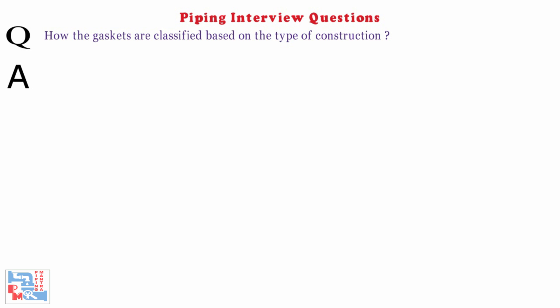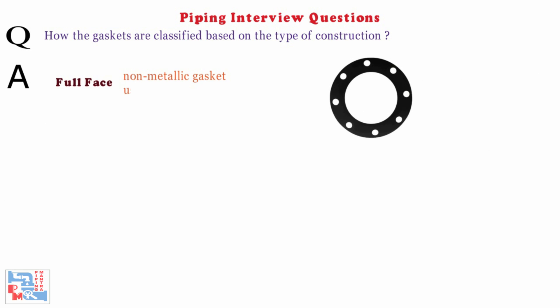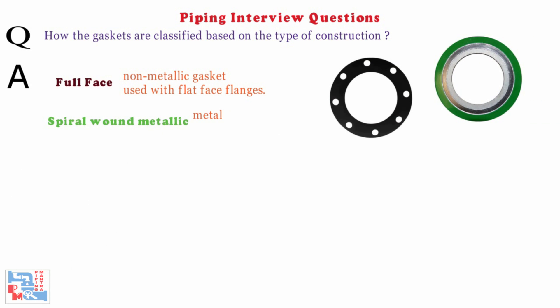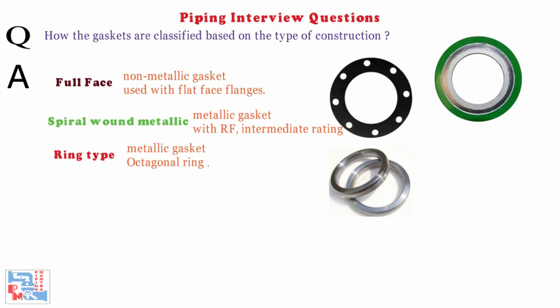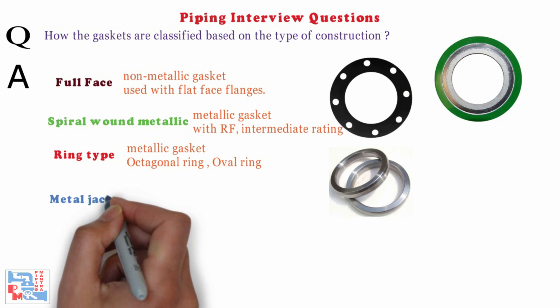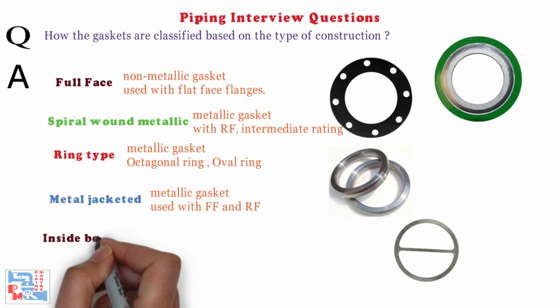Next: how are gaskets classified based on the type of construction? Based on type of construction, gaskets are classified as: full face — a non-metallic gasket used with flat face flanges; spiral wound — a metallic gasket used with raised face at intermediate ratings; ring type — a metallic gasket with two types, octagonal ring and oval ring; and metal jacketed — a metallic gasket used with flat face and raised face, sitting inside the bolt circle.